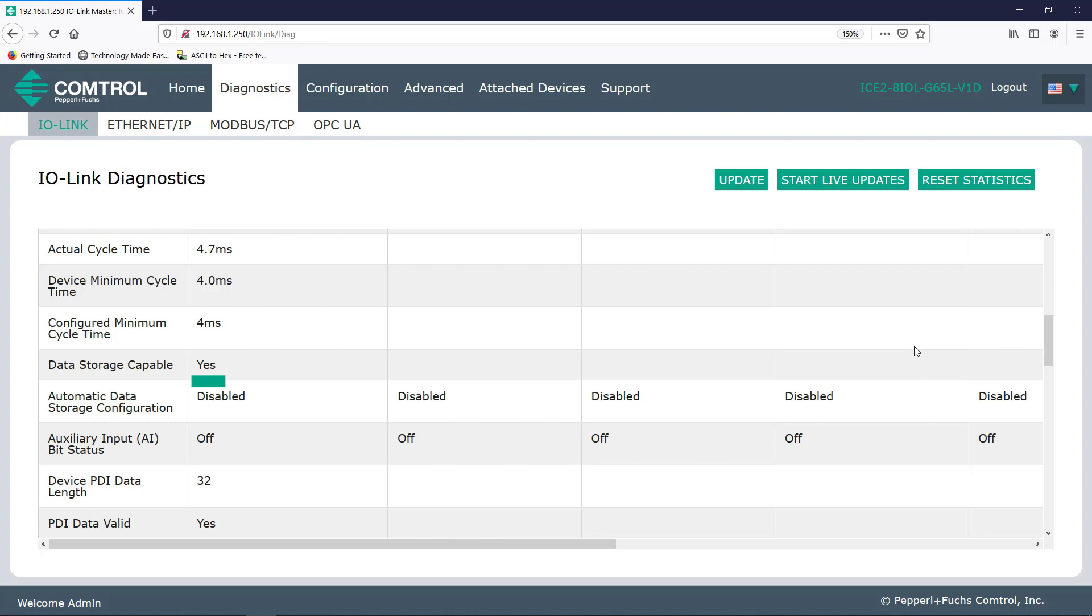So basically, with this feature enabled, the port can automatically upload data from the IO-Link device and or download data from the IO-Link master. Remember though, that not all devices are capable of doing data storage. Again, the automatic data storage configuration can be set on the configuration tab. Depending on what you set, this field may either say upload, download, or both.